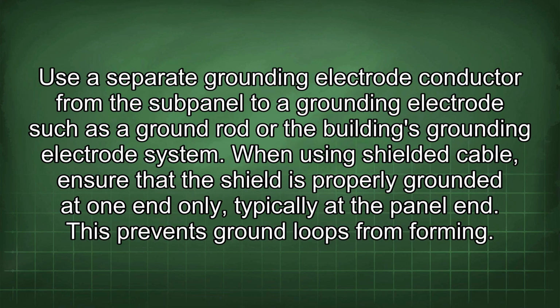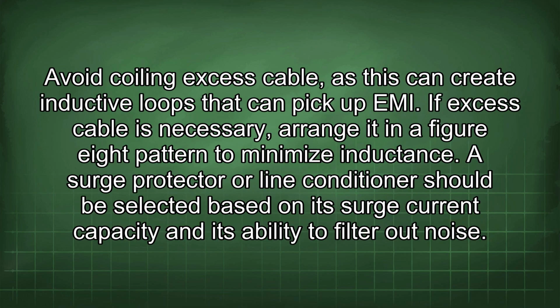Use a separate grounding electrode conductor from the subpanel to a grounding electrode such as a ground rod or the building's grounding electrode system. When using shielded cable, ensure that the shield is properly grounded at one end only, typically at the panel end. This prevents ground loops from forming. Avoid coiling excess cable, as this can create inductive loops that can pick up EMI. If excess cable is necessary, arrange it in a figure 8 pattern to minimize inductance.